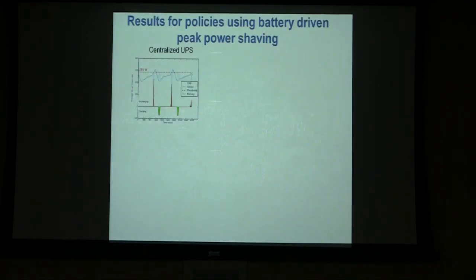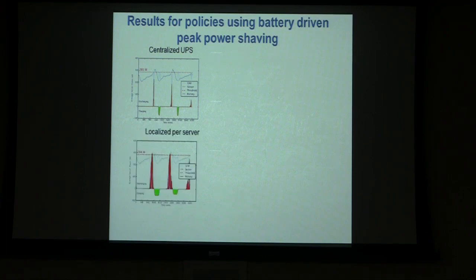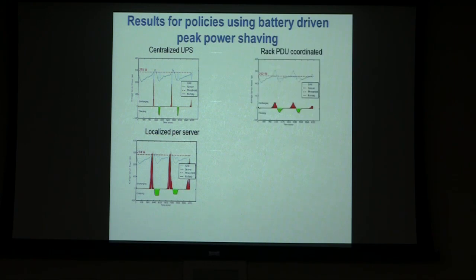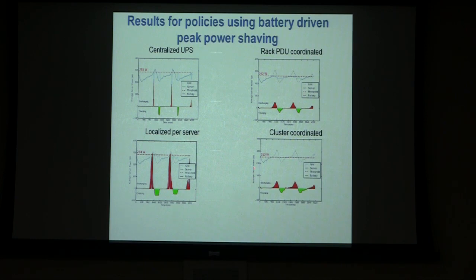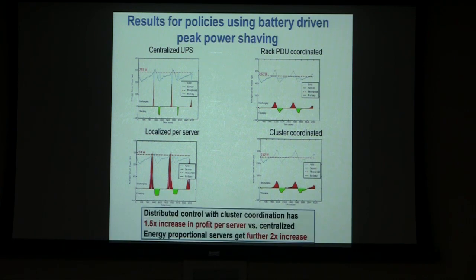First we looked at centralized UPS, and here the maximum peak power we could shave down to was 285 watts, not much out of a 300-watt server, due to the inefficiency of a fully centralized policy. If you go fully localized, you also have a problem, because now there's no concept of what else is going on around you, so you start shaving power as soon as it hits whatever peak was defined. Much better behavior comes from rack level and cluster level: at cluster level we're down to about 252 watts, about 50 watts less than the original, giving much longer durations of power spikes than we could otherwise have.